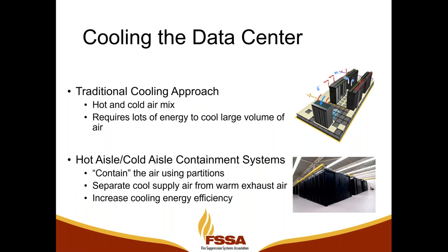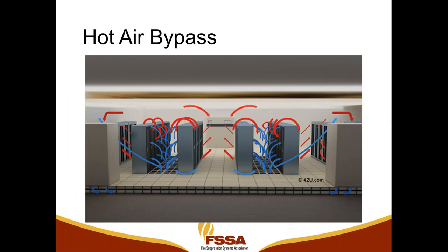So a new strategy needed to be developed, and that is hot aisle, cold aisle containment systems. In this strategy, we add new devices into the data center to help contain the air, to directionally route the air to cool the equipment and separate hot air from cold air. Without aisle containment, we get a phenomenon called hot air bypass. As the cooling airflow increases, sometimes hot air will come from the hot aisle and short circuit back to the front side of the cold aisle.